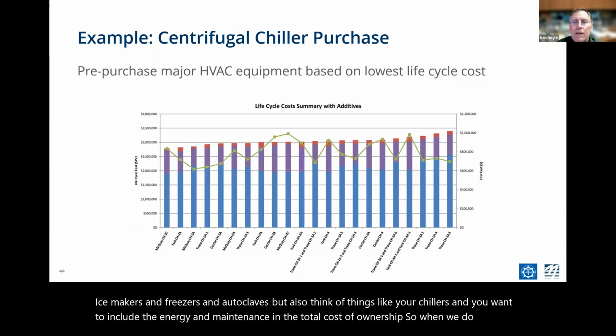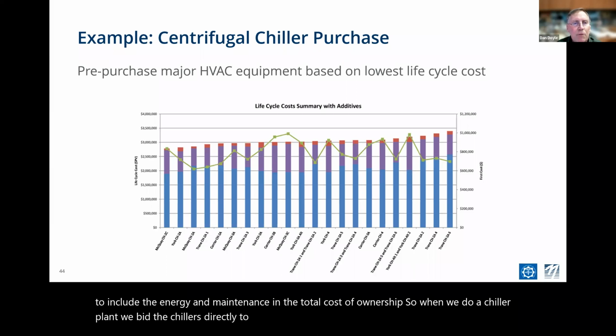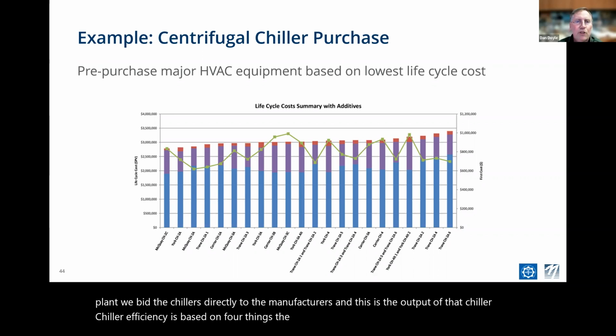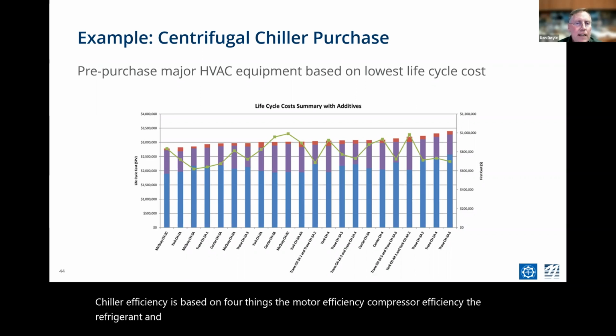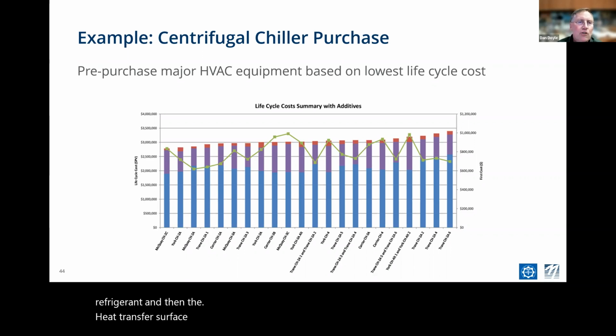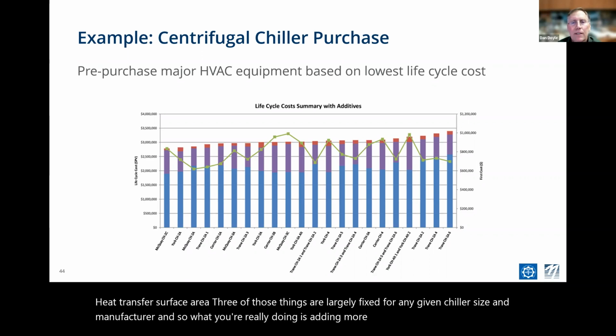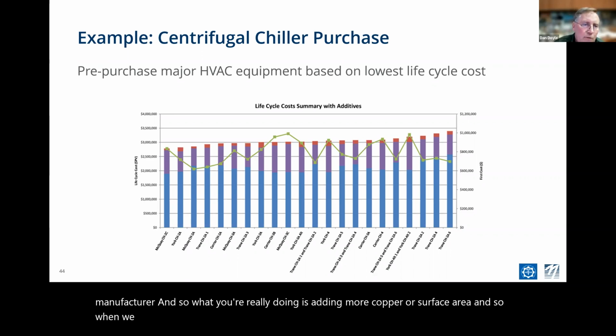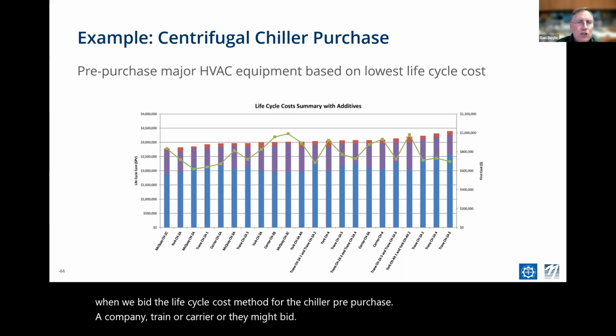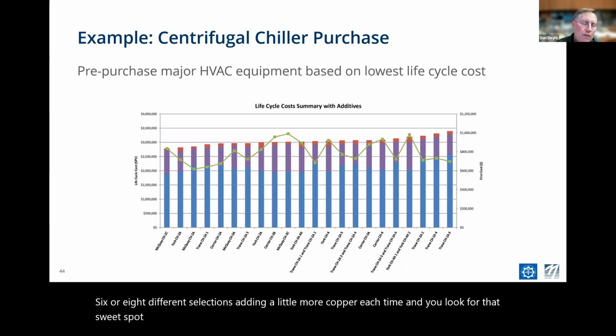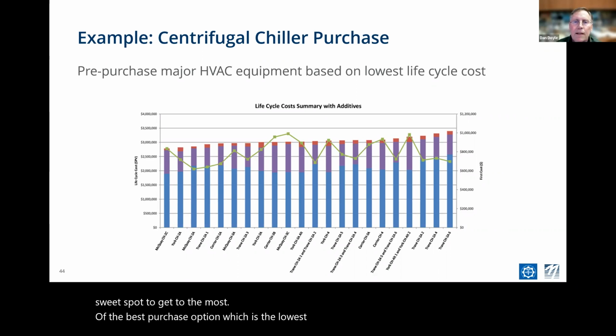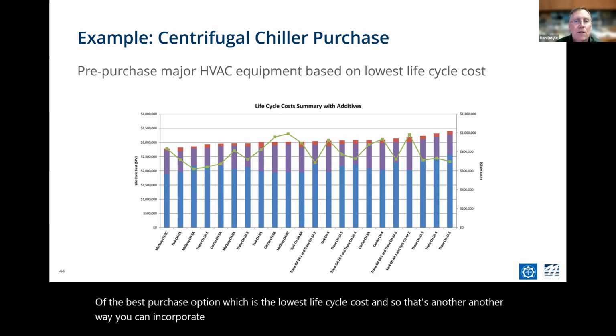So when we do a chiller plant, we bid the chillers directly to the manufacturers, and this is the output of that. Chiller efficiency is based on four things: the motor efficiency, compressor efficiency, the refrigerant, and then the heat transfer surface area. Three of those things are largely fixed for any given chiller size and manufacturer. And so what you're really doing is adding more copper or surface area. And so when we bid the life cycle cost method for the chiller pre-purchase, a company like Trane or Carrier might bid 6 or 8 different selections, adding a little more copper each time, and you look for that sweet spot to get the best purchase option, which is the lowest life cycle cost. And so that's another way you can incorporate life cycle costing into your energy efficiency program.